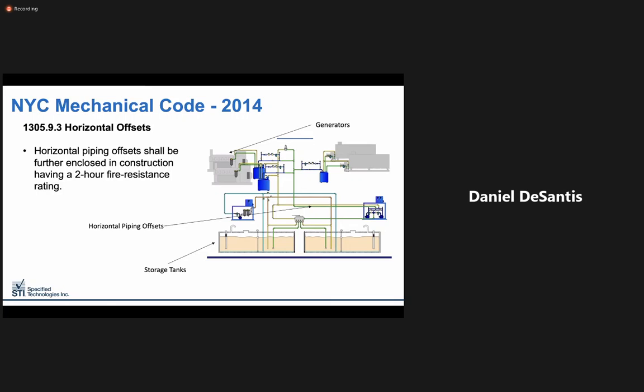This would produce a lot more horizontal offsets as piping is run from the subcellar storage tanks to the rooftop generators. Where piping turns out of a vertical shaft to another vertical shaft would be considered a horizontal offset. The use of endothermic wrap can be used in conjunction with both CMU and gypsum wallboard assemblies. We'll be breaking that down a little bit further in a bit.